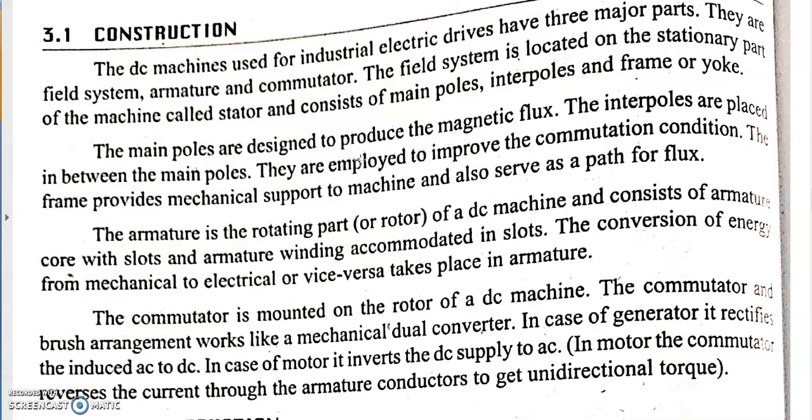The field system is the stationary part and also the outermost part of the machine. Being stationary, it is also called the stator. It consists of main poles, inter poles, frame, and yoke. The main poles are designed to produce the magnetic flux. The inter poles are placed in between them to improve the commutation condition. The frame provides mechanical support to the machine as well as a path for the flux.